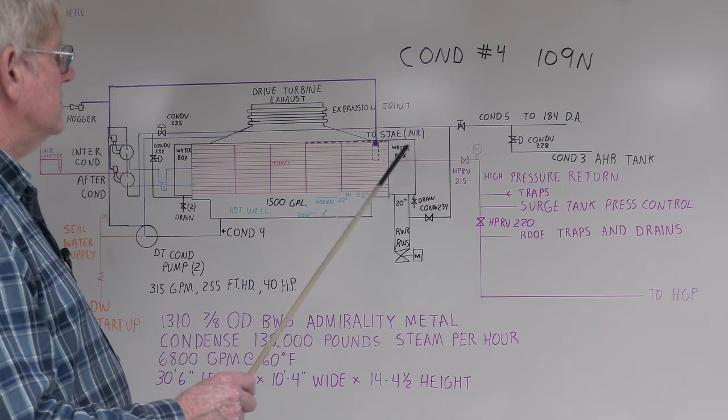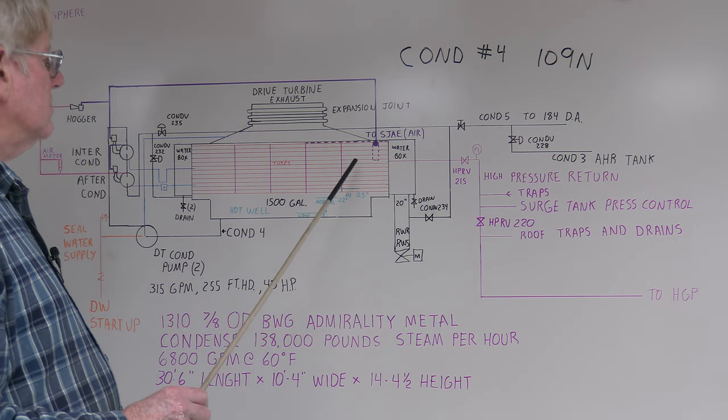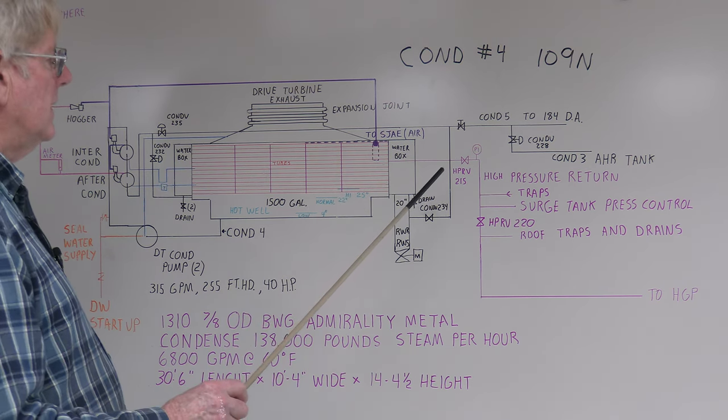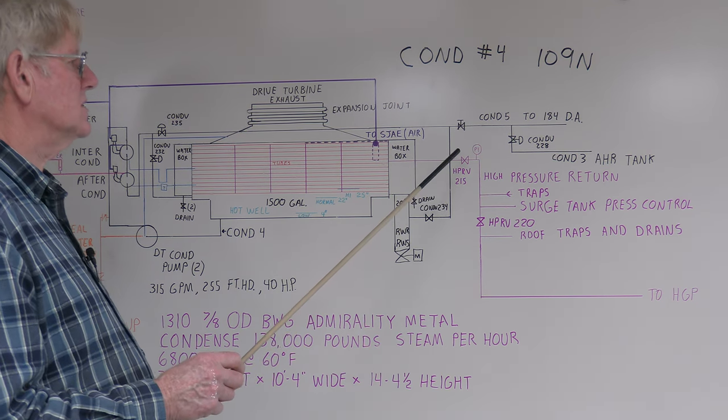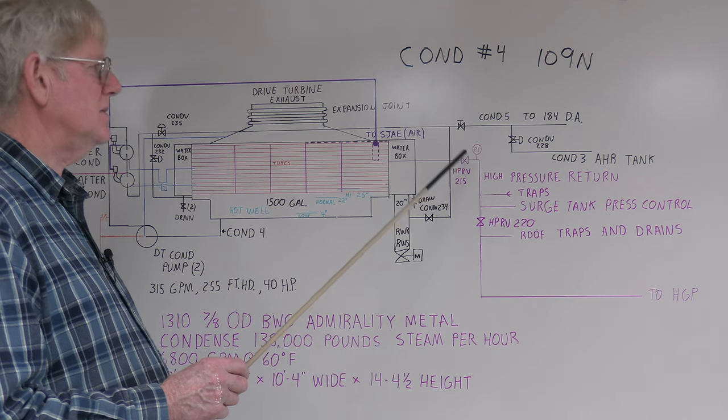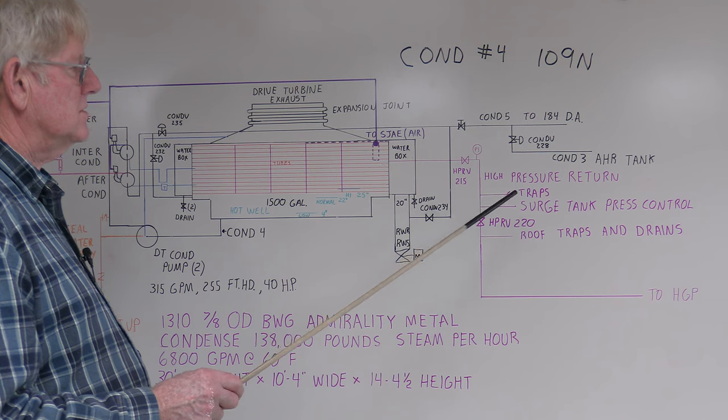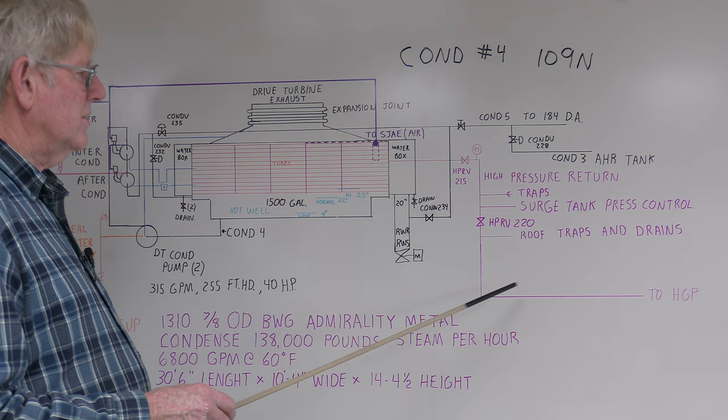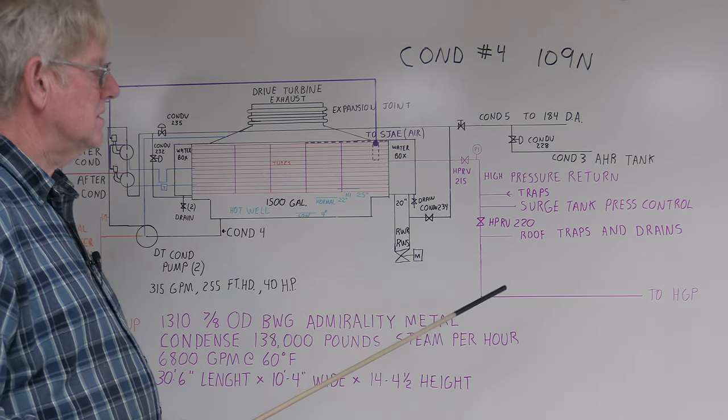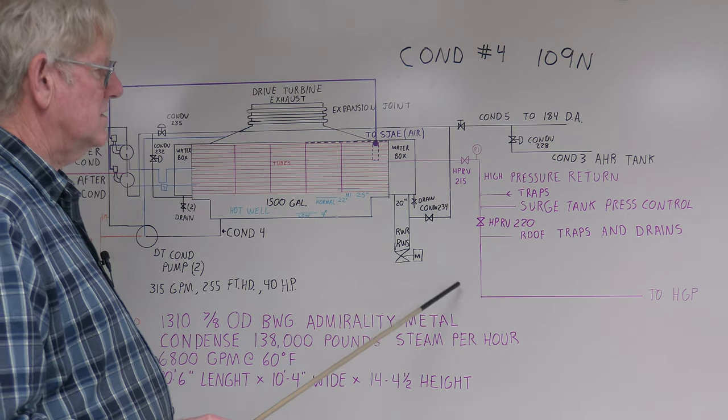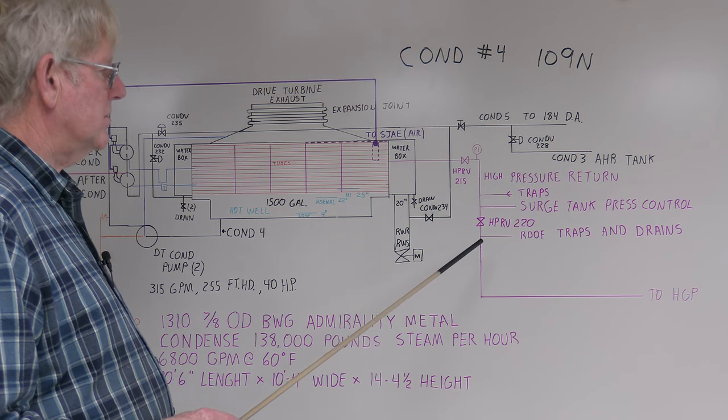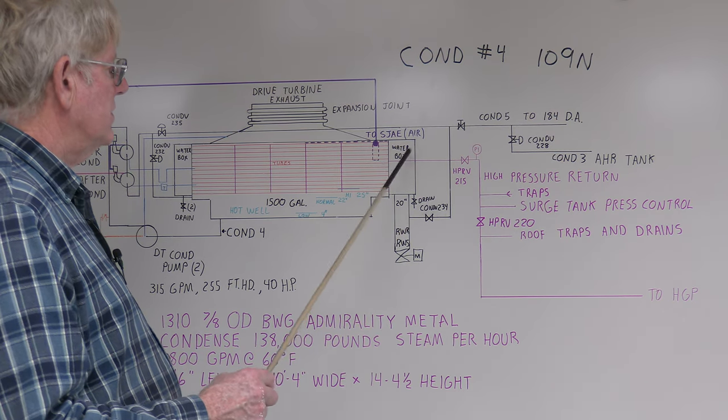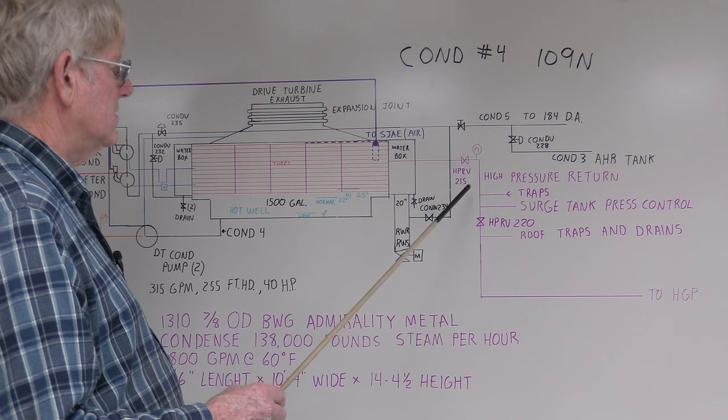Another part of this: you had your high pressure return came back in. I believe that there were just two surface condensers valved in for high pressure return. I'm not sure what the pressure was - there was a manual valve that had to be adjusted. I think it was between maybe 9-15 pounds. You had all your traps, surge tank pressure control, roof traps and drains would come back into this. I know the Hanford generating project took a lot of the high pressure return to number one and two surface condensers. They had a control valve. I think all the roof traps and drains went back over there. For startup we could take it back here, but I know we did bring some back - it's probably just our traps and local drains.